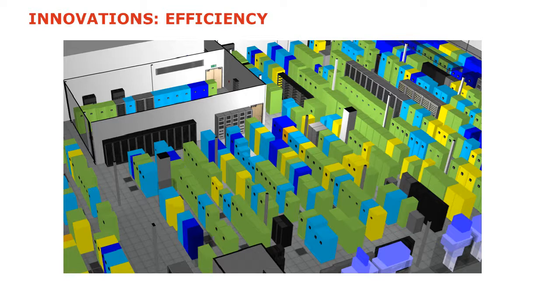Absolutely, yeah. Thanks, Steve. So what this picture represents is the temperature of each of the cabinets. For those of you not familiar with the data center, the way we tend to organize IT equipment is to put them into standard sized cabinets or racks within the data center. The idea is that we have an airflow through those cabinets, through the IT equipment. We put cold air in one side, ideally, and there is a set of temperature envelopes that we are required to operate within to make sure the IT equipment is properly cooled. Then essentially the air will pass through that equipment, come out of the backside as hot air, and hopefully be extracted or removed into cooling units to be recirculated. That's typically the way it works in very simple terms.